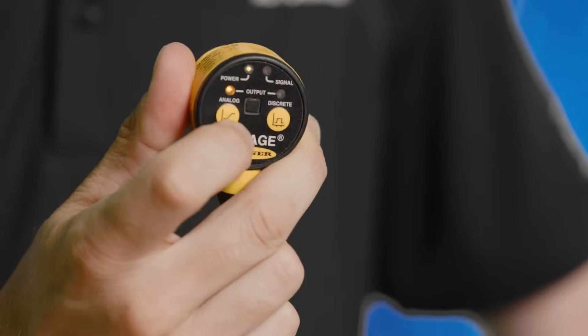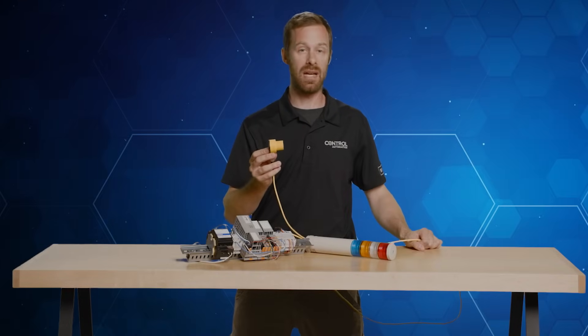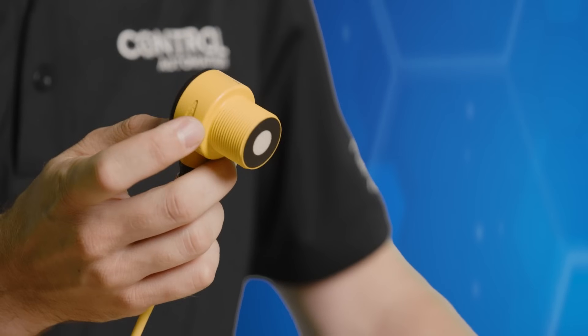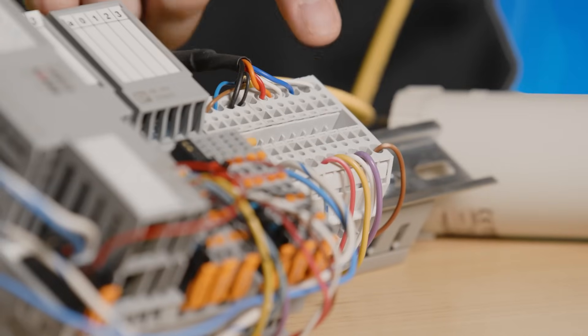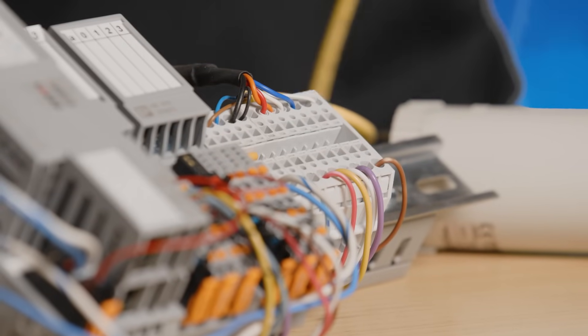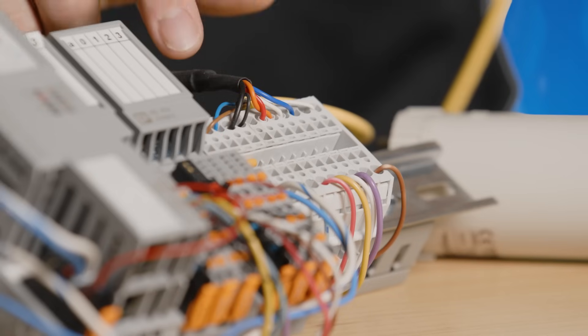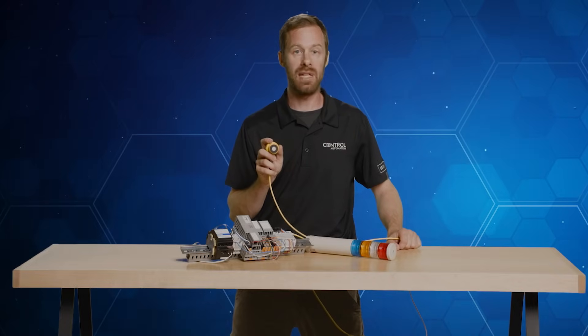There are two LEDs that provide output indicators for both our discrete signal and our analog signal. While we monitor the PLC program and can see the bits and words of information changing, we can monitor those LEDs on the back to make sure they're giving the right indication. The black wire in our sensor is connected to the discrete signal — very common for the quick disconnect structure. The white wire from this Banner U-Gage sensor carries the analog signal and goes to the analog module of our PLC. The blue and brown wires indicate the power input from our DC power supply. Most of these sensors are powered between 10 and 30 volts DC, though some can accept AC voltages and different DC voltage variations depending on the system.